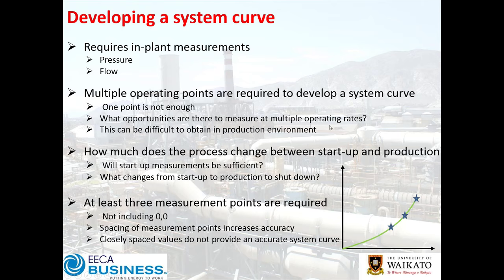In a production environment this can be a challenge. Cleaning cycles, end of run, start of run — there are creative ways to identify and get these figures. Startup, production, and shutdown can provide chances to get those additional points. Be mindful that startup, shutdown, and production could have different particulate loading, which can change things. For example, a cyclone with clean air has quite a different pressure drop than with particulate loading — interestingly, with particulate loading the pressure drop can actually go down rather than up.